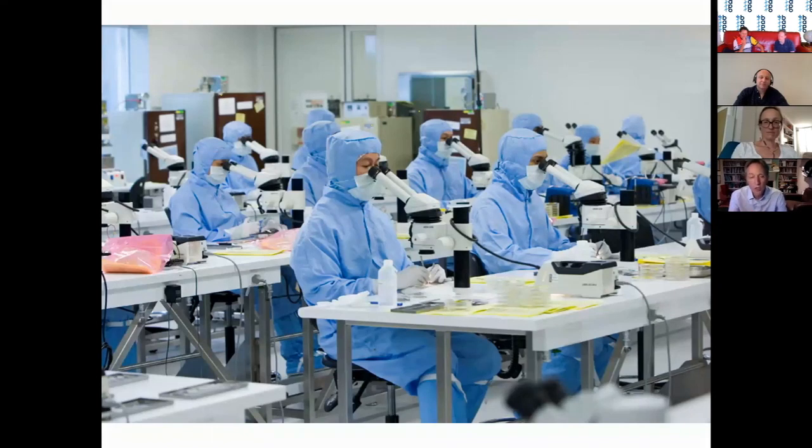You must have something that in 10 or 15 years' time you or a colleague will be able to take out and change. Different hospitals and different countries have quite different patterns of electrode use — it probably comes down as much to financial considerations as anything. If you go to Austria, everyone gets one type of electrode; in Australia, everyone gets another. It's not that Austrian children are different from Australian children, it's just the way it happens. Broadly speaking, you either have perimodiolar electrodes with some sort of spring mechanism that tightly hugs the modiolus, or lateral wall electrodes. The thought with perimodiolar is that, like a child holding a torch, the further away you are, the wider the spread — so a lateral wall electrode has more spread. However, you are less likely to damage residual hearing with a lateral wall electrode.